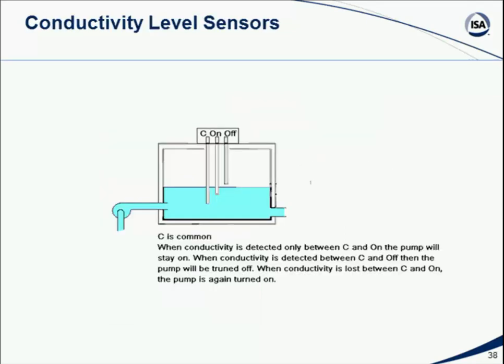There are other types of technologies that work on similar properties. One, a very simple one, is conductivity. If I've got a fluid that, in fact, is conductive, then I can put a series of metal probes down into the tank. Of course, they have to be insulated from the tank at different levels, and I can measure the resistance between those various probes. And as the fluid level rises or drops in the tank, I can determine how high the level is, knowing the lengths of my probes, because, for example, in this case, as the fluid level reaches up to where the C probe and the on probe are both covered, I'll measure a resistance between the two of those that has just dropped because the fluid's conductive.